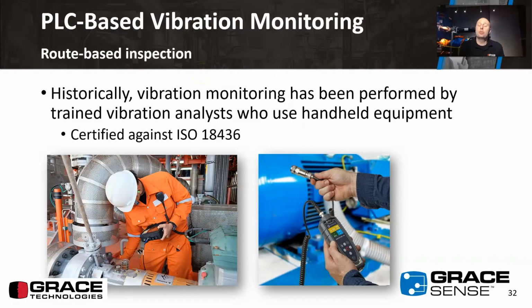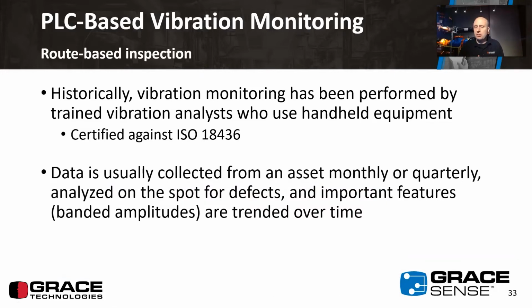Historically, vibration monitoring has been done by trained vibration analysts who physically walk through your facility using handheld equipment and take measurements. These are typically collected monthly or quarterly and analyzed for defects: did we see a spike in the bearing band, or an increase in amplitude associated with the run speed of that equipment? That data is captured over time to see if amplitudes are increasing, which can be indicative of problems.